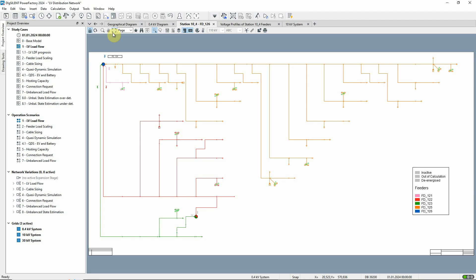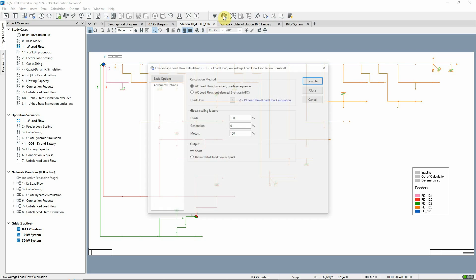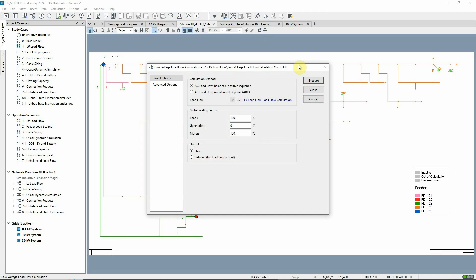We can now execute the low voltage load flow calculation. The command can be found in the distribution network analysis toolbox. In this example, we want to account for the worst consumption case, and so have scaled the generation elements in this network down to zero in order to analyse the capability of the network to supply the demand.